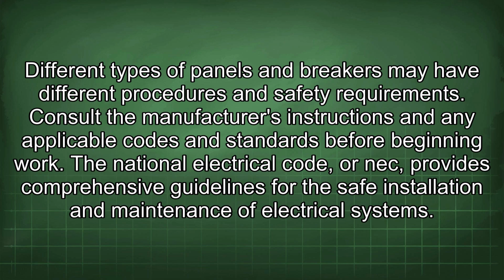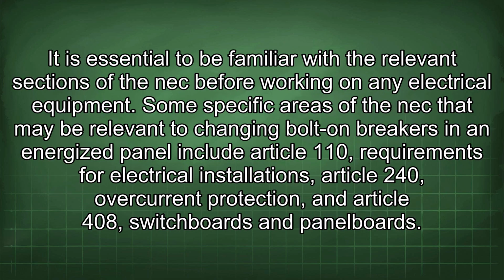The National Electrical Code, or NEC, provides comprehensive guidelines for the safe installation and maintenance of electrical systems. It is essential to be familiar with the relevant sections of the NEC before working on any electrical equipment. Some specific areas of the NEC that may be relevant to changing bolt-on breakers in an energized panel include Article 110, Requirements for Electrical Installations, Article 240, Overcurrent Protection, and Article 408, Switchboards and Panel Boards.